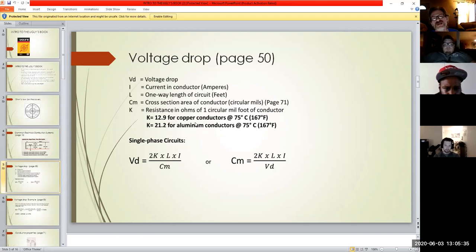Hopefully it's copper because I can't stand aluminum, but if you're stuck using aluminum, you can do the calculations for it too. They use a standard temperature for our region, 75 degrees Celsius. If you move somewhere else, like Arizona, you'd have to account for the temperature there since they're dealing with hotter conditions, so you'd use a different part of the chart.